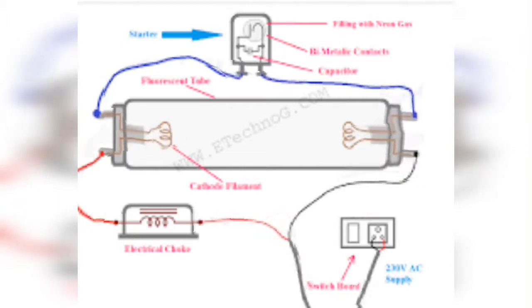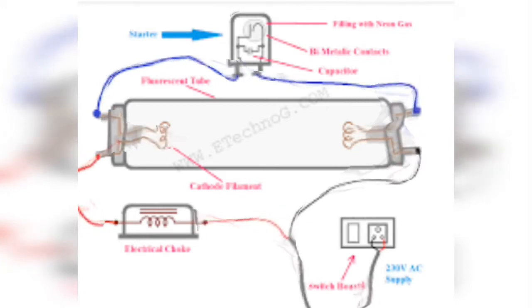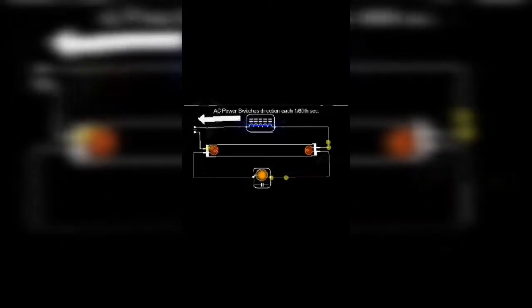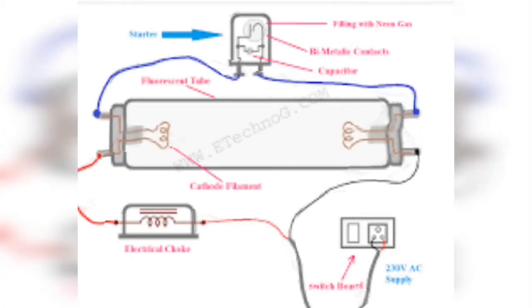The function of a choke is to provide the high voltage needed for ionization to take place in the tube. After ionization is established, it limits the voltage across the tube. That is the reason why a tube fuses when the choke is shorted.